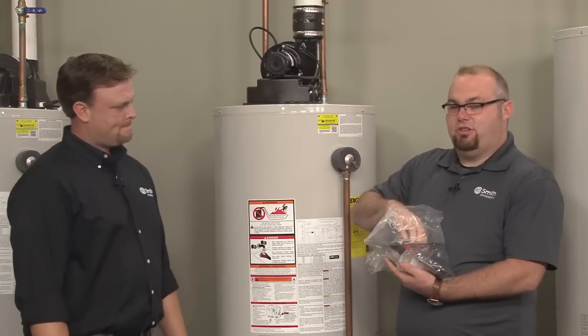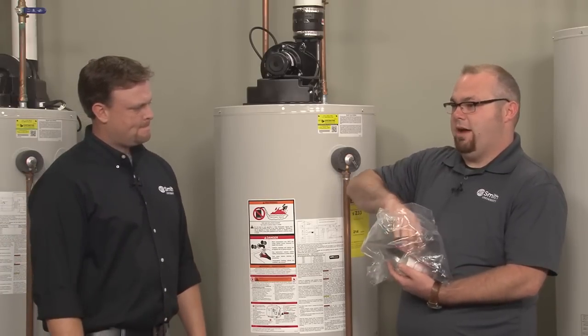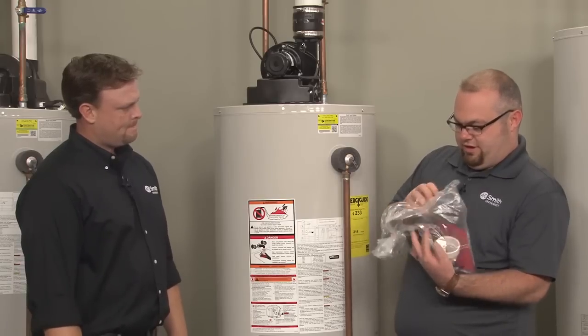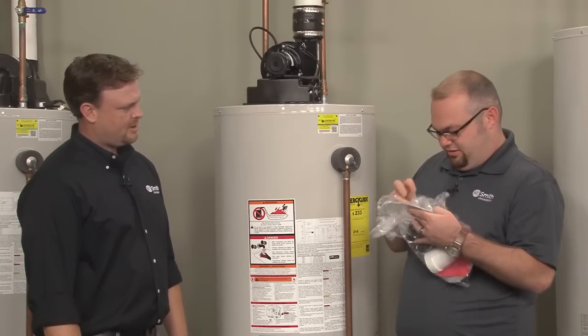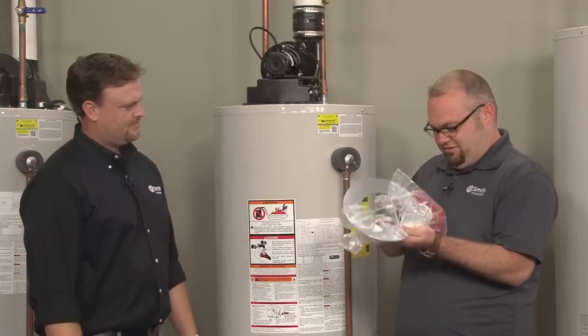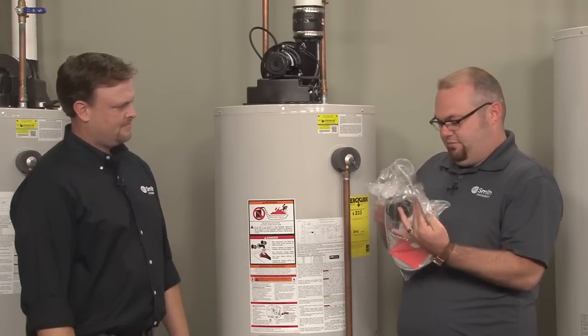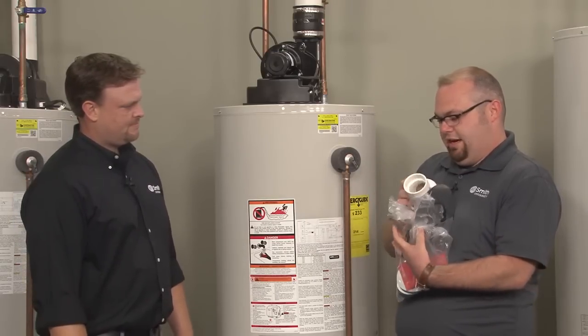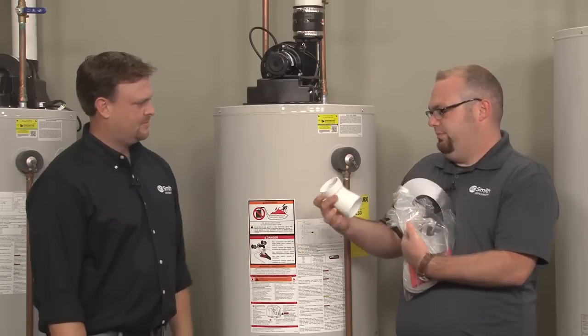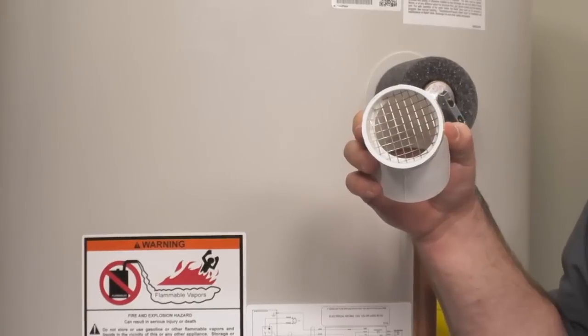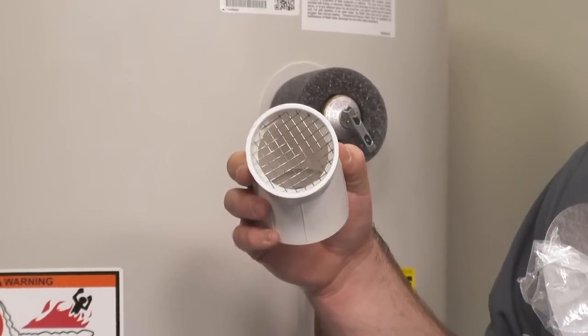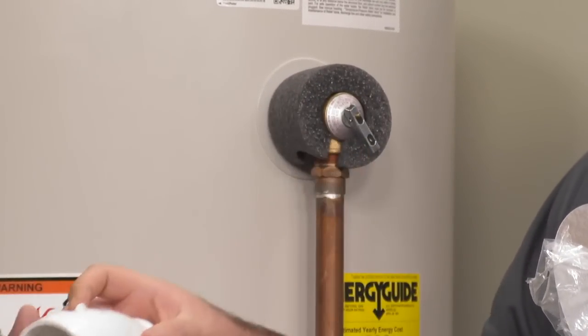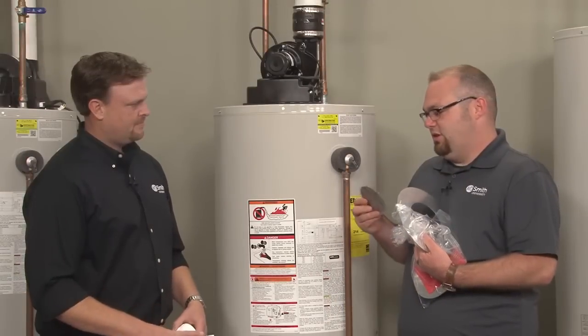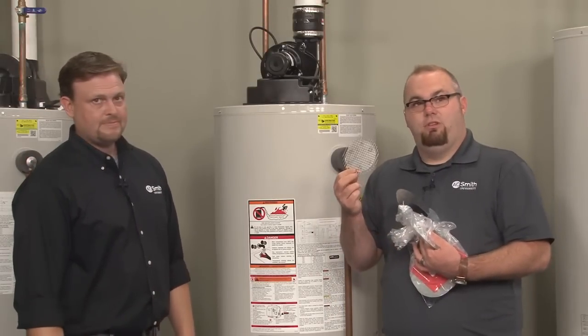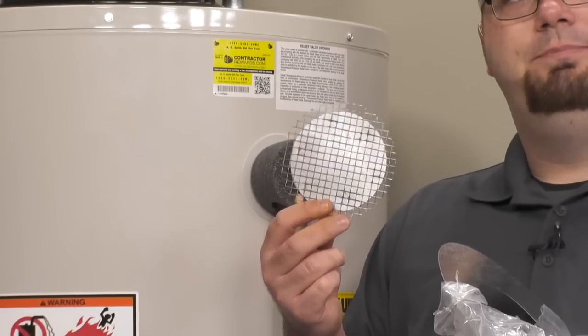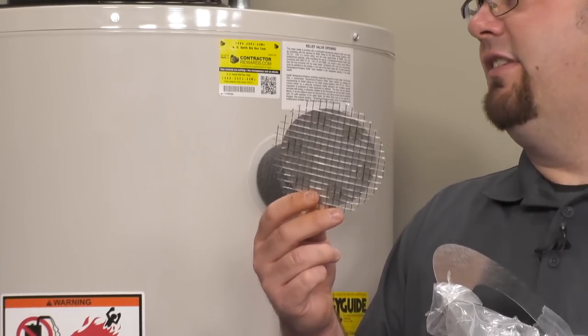In the past, your termination screen that pretty much all power vents came with, if I can get one of them out. There you go. They would just come with a rodent screen, like what you see here. It's just nothing more than a stainless steel screen. Some of the other terminations this one comes with now is like this one. For a 4-inch vent run, I believe it's typically under 50 feet.